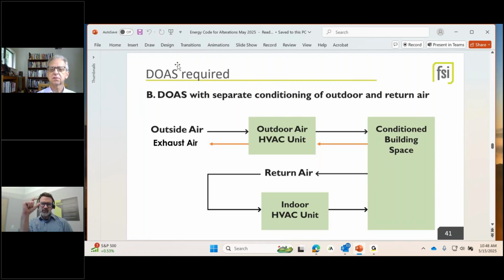HVAC equipment tends to be notched. There is a capacity and then another 150% of that capacity, 200% of that. So often, yes. The outside air and the latent loads of the space, because we're doing energy recovery and getting the humidity part down, can drop so dramatically that even though we've now got 2 pieces of equipment, our total electric demand and certainly electric use are lower. Our equipment sizing and HVAC loads are lower, and you've got to watch yourself on HVAC loads for the non-mechanicals in the room. There's a lot of ways to move that number around. But yes, generally we are smaller now than we were. We're one size smaller when it works. If we were right up against the capacity, sometimes it's not. But mostly, yeah, we get to downsize a little.